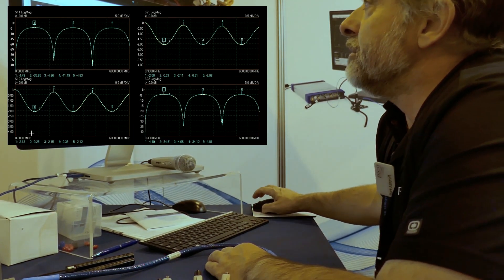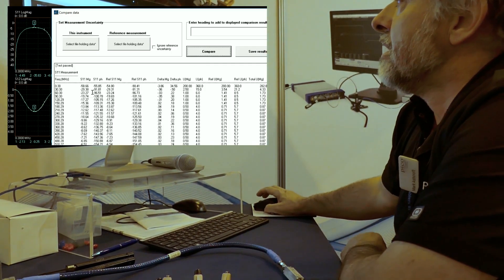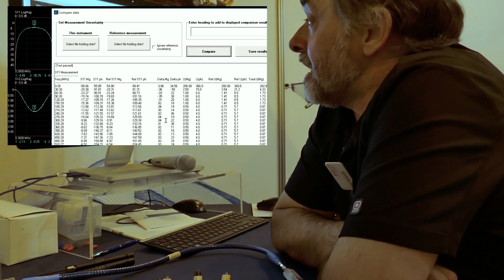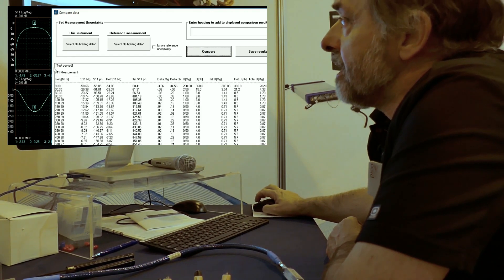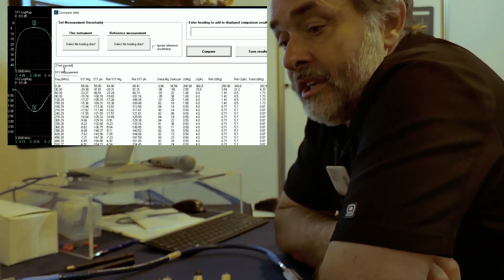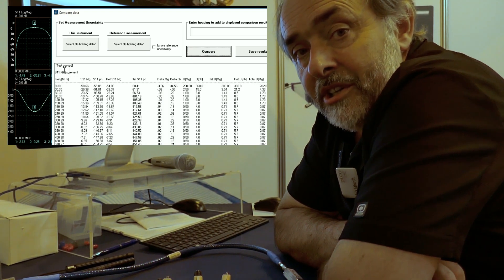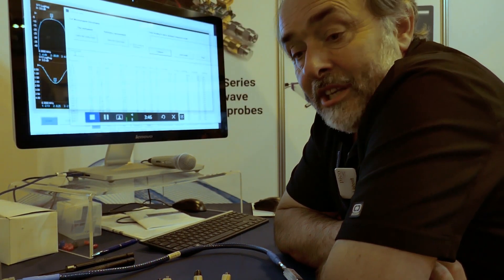That's our live trace. We can compare that if we use the compare data utility and compare. And what that's doing is it's comparing the blue data with the yellow data and it's telling us, as we can see here, test passed. That is comparing the measured data with the traceable data provided with the check standard, and that's telling us that we are within uncertainty with that measurement at the moment.